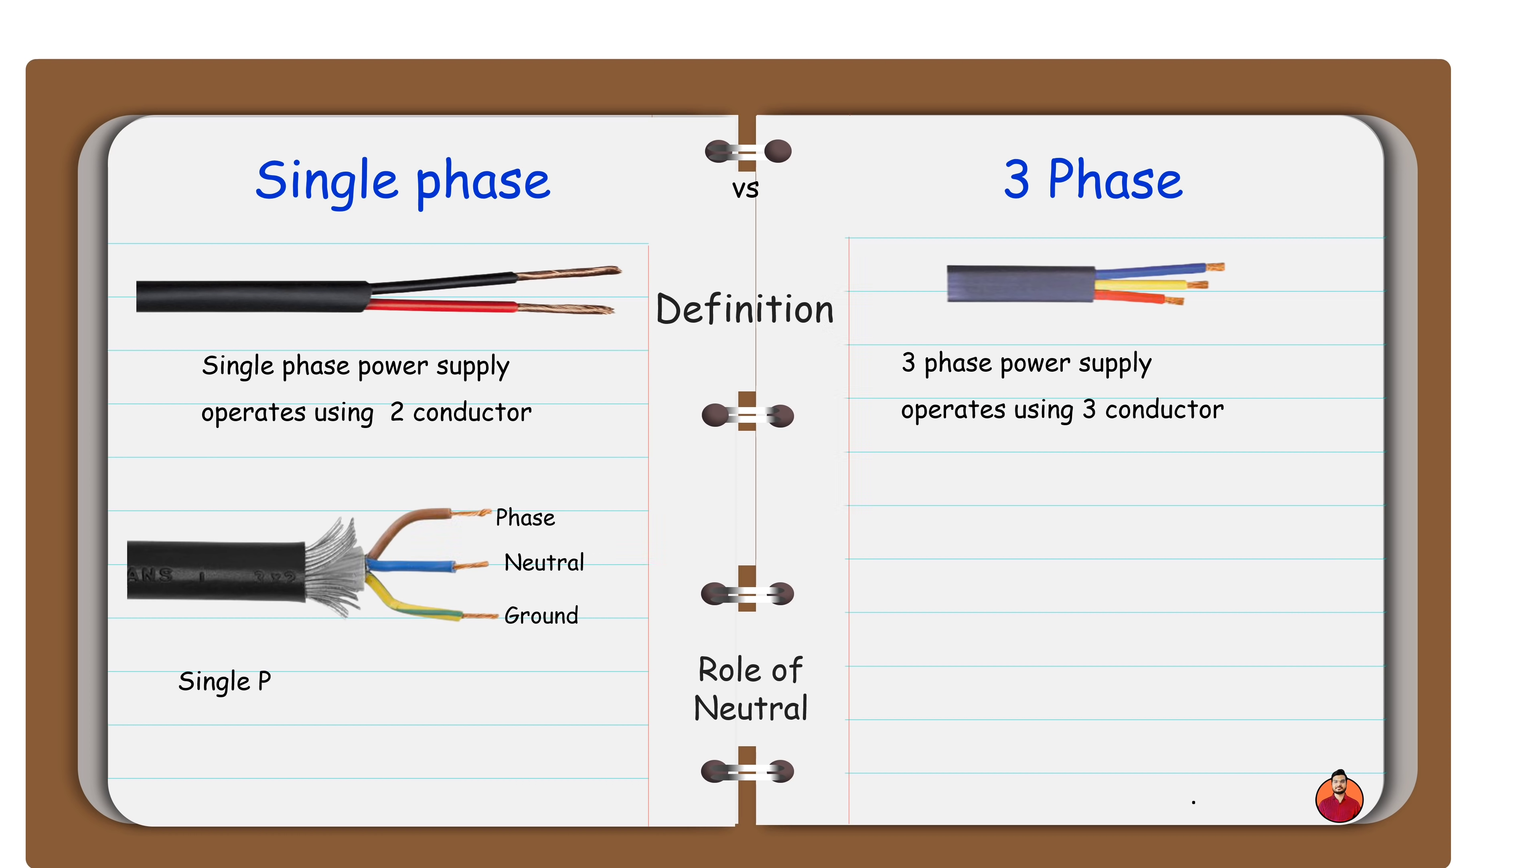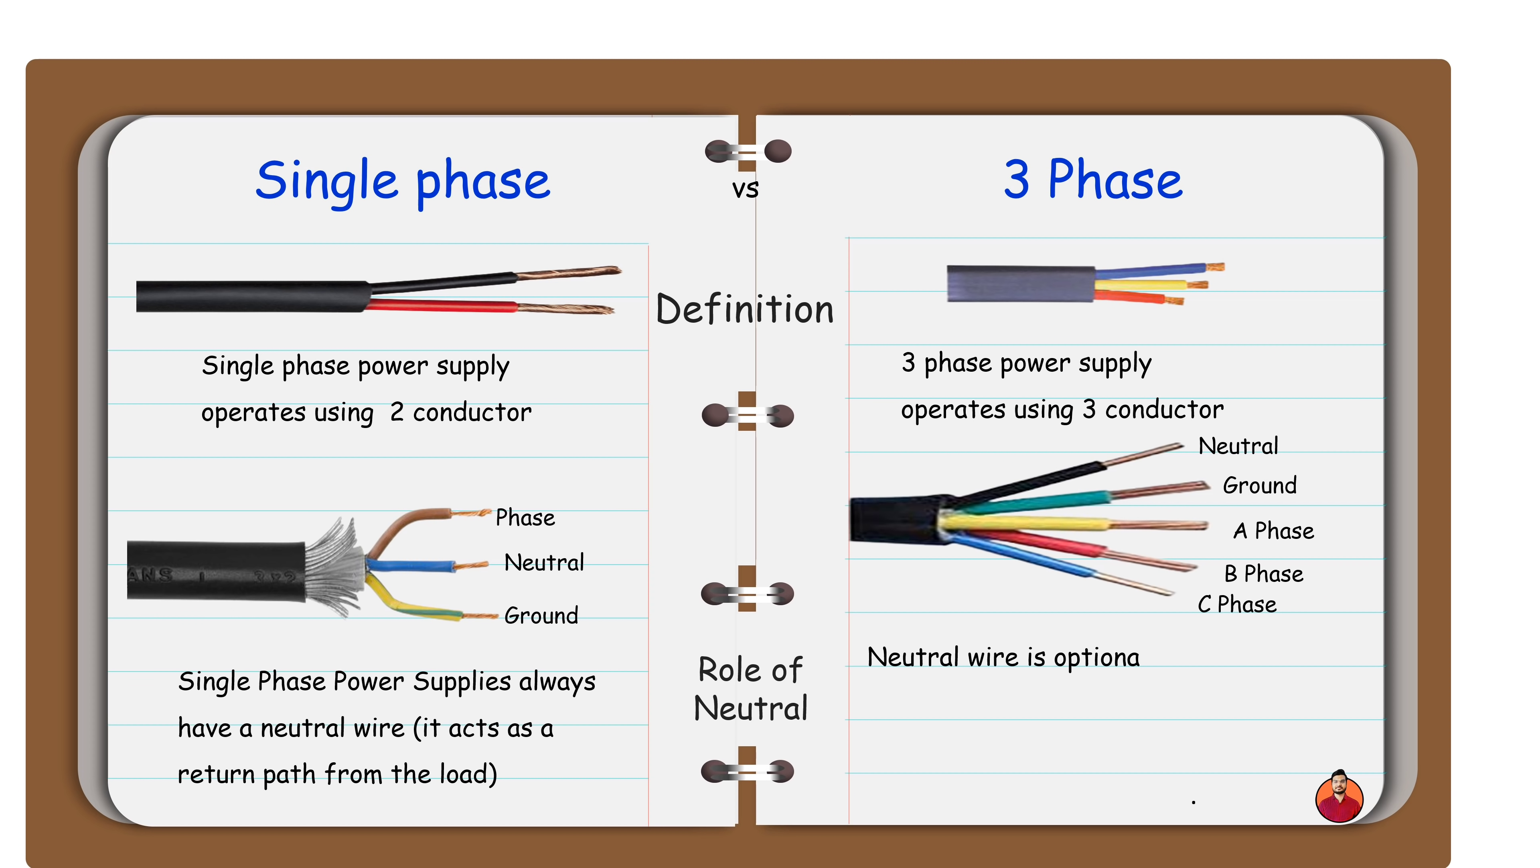Single-phase power supplies always have a neutral wire. It acts as a return path from the load. A neutral wire is optional in three-phase power supplies. Delta connections have no neutral wire, but star connections may or may not have neutral wire.